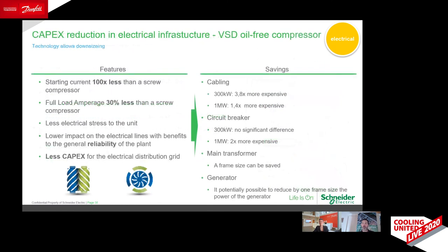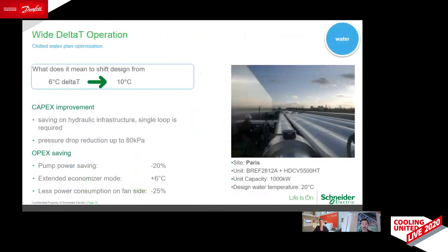From the compressor point of view, certainly Turbocor, when compared to screw compressors, can help on this. The amperage and starting current allow a lot of savings on the electrical infrastructure, on the genset, on the transformer. So if you have to make a choice, when you look at the overall investment, we need to look at the cost of the unit, but we also need to look at the capital expenses for the entire data center. This is the same on the water side.